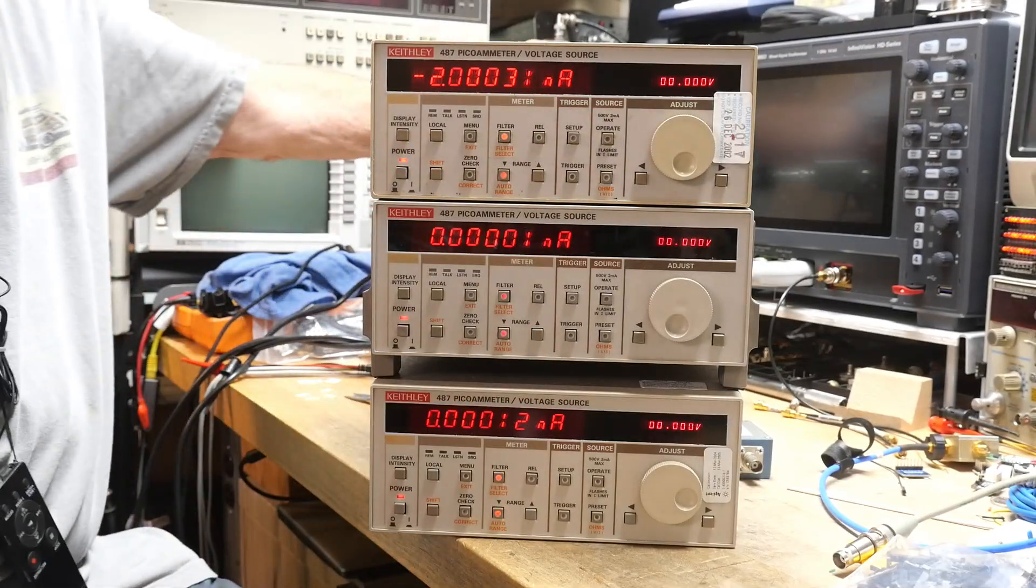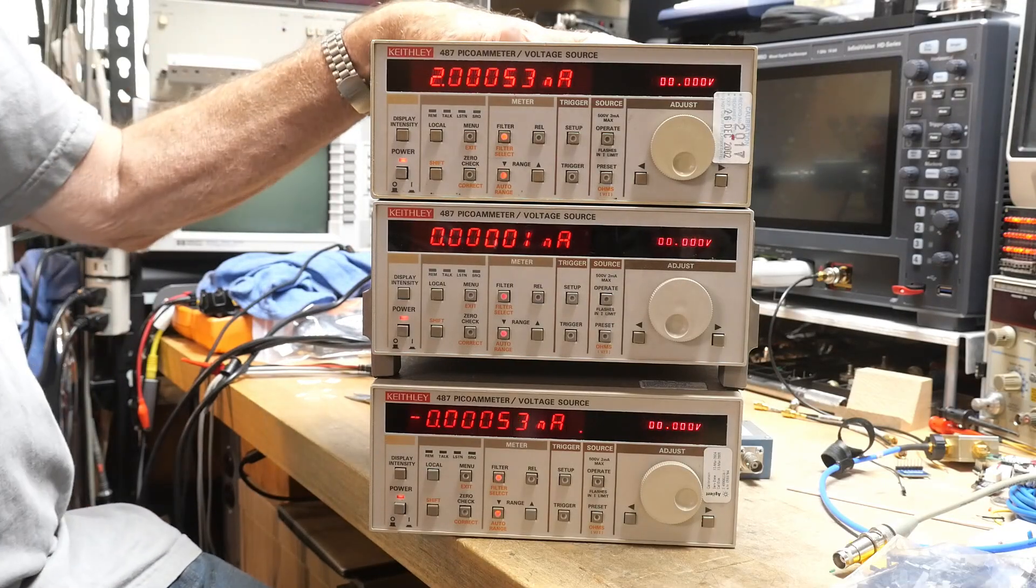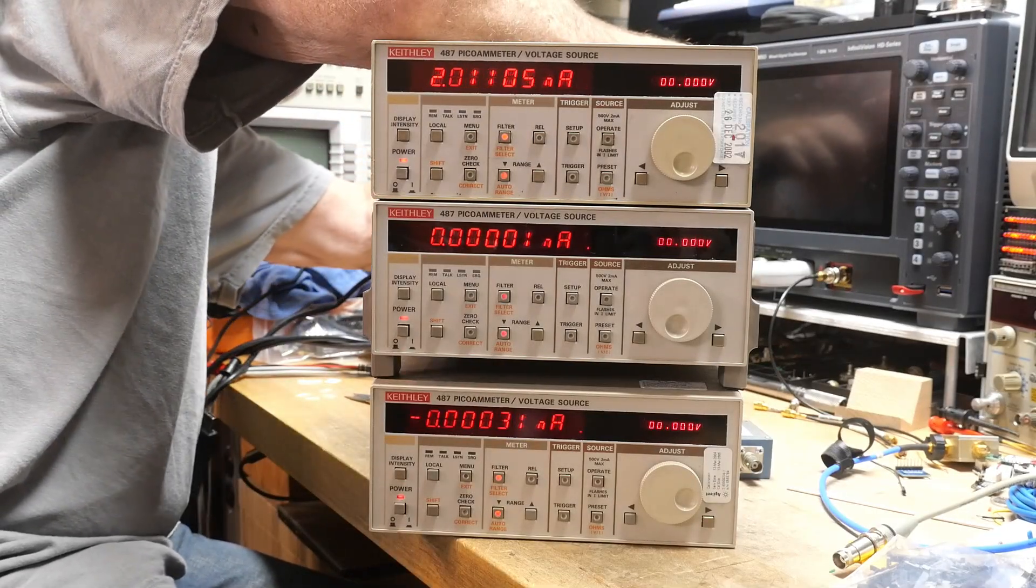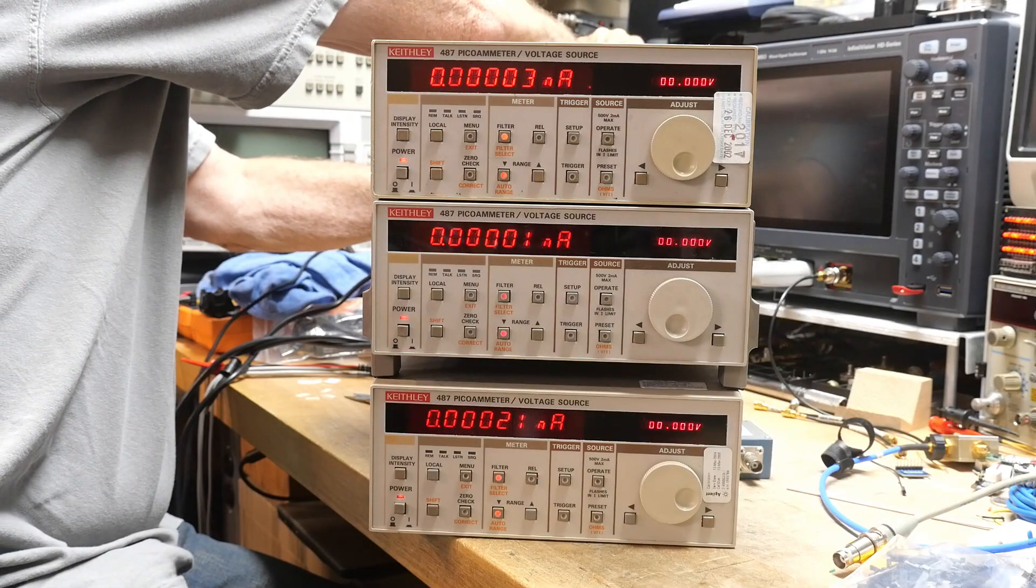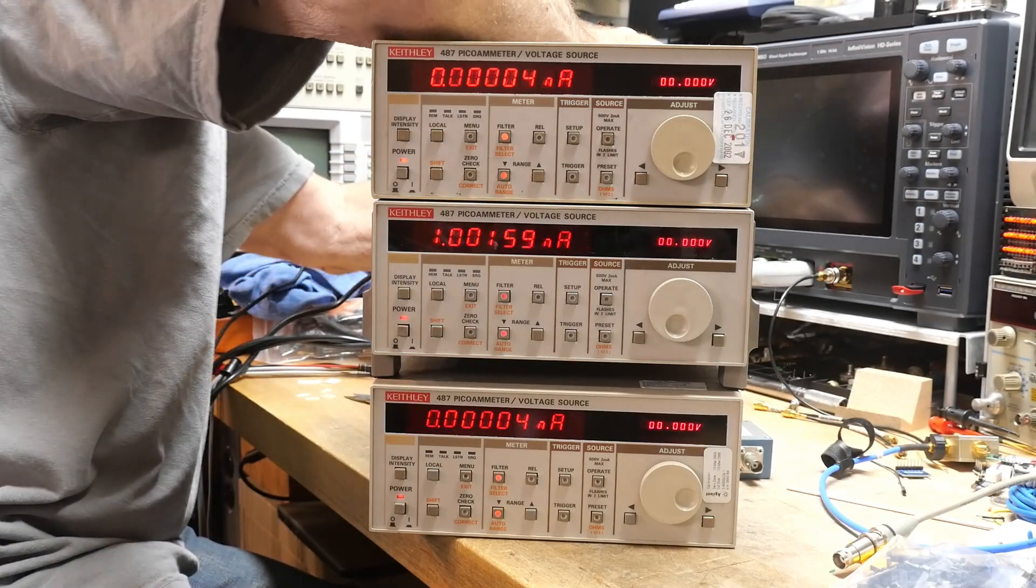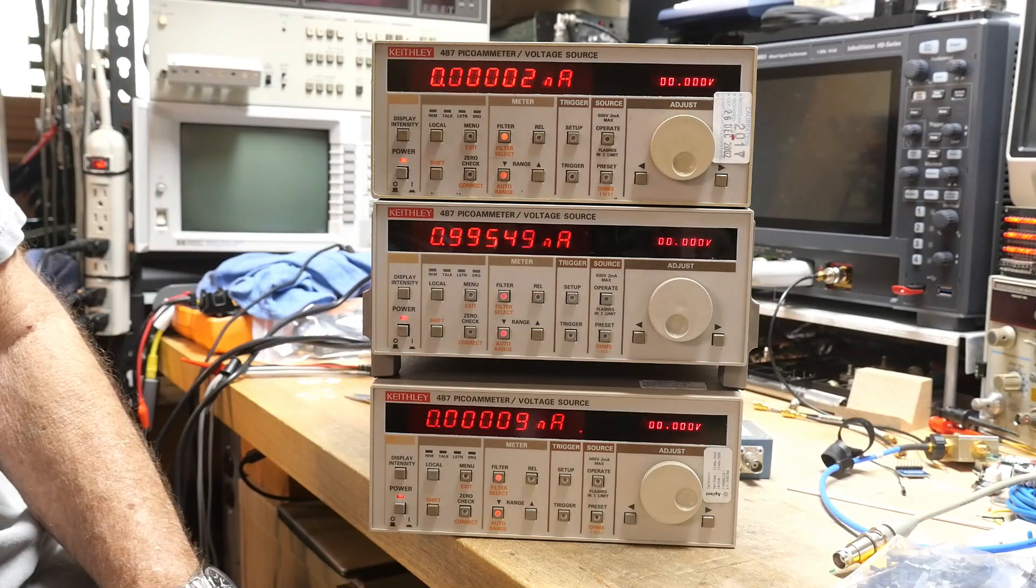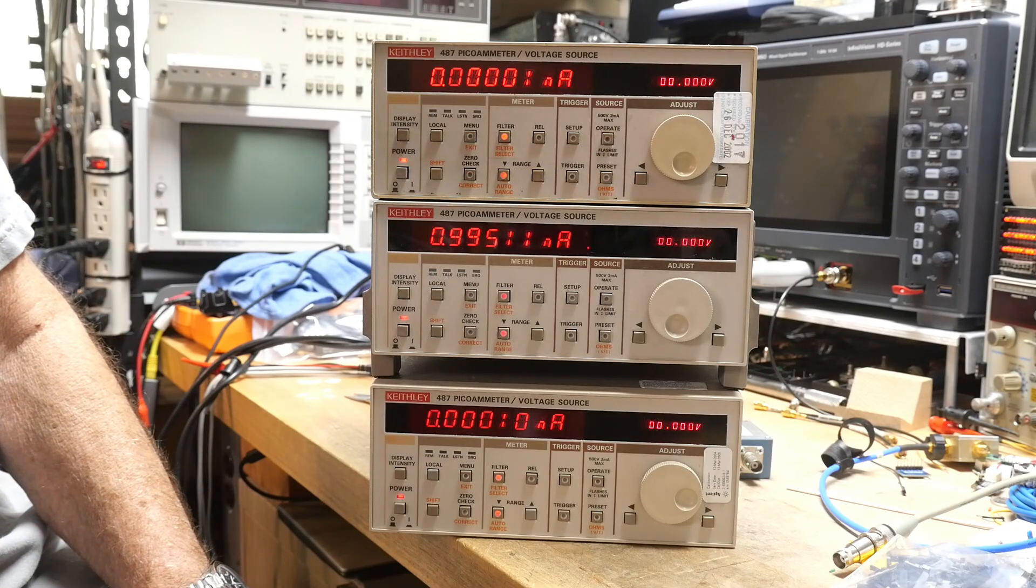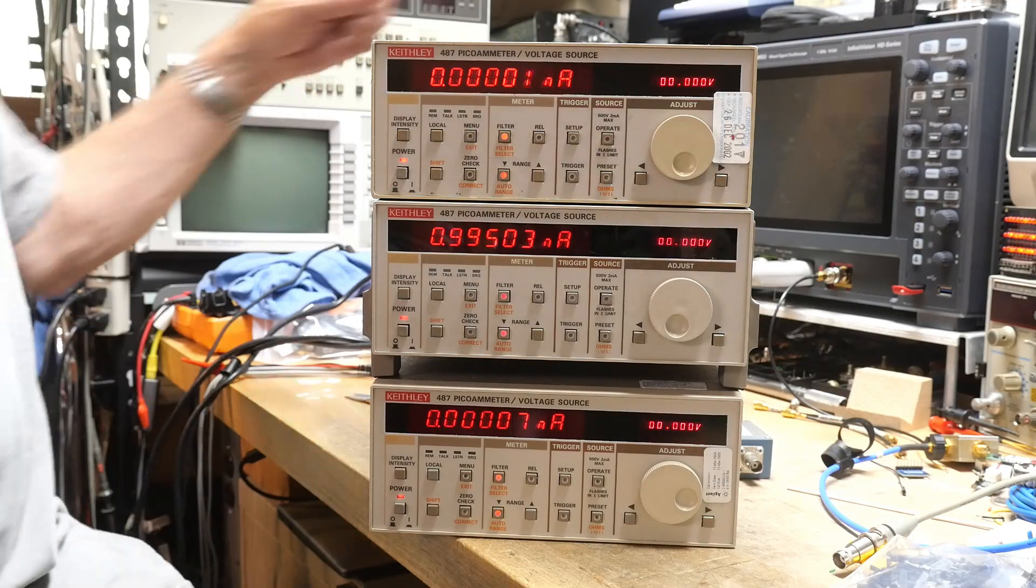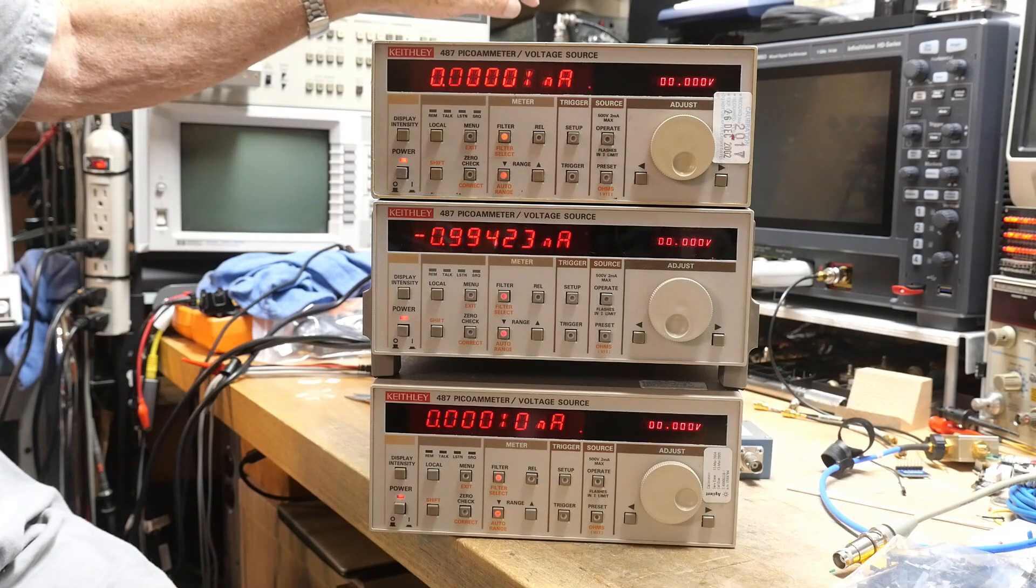So instead of looking at digits way up there, you should be looking at digits kind of in here for absolute accuracy. And then for relative stability and things, look at the more digits. So yeah, I think minus two plus two. Yeah. I think this one seems to be doing that test pretty good. Let's move down to the next one. Set it here to one volt again. All right. Well, this one's reading a little bit lower. Let's do a negative voltage. Yeah. It just reads a little bit lower.